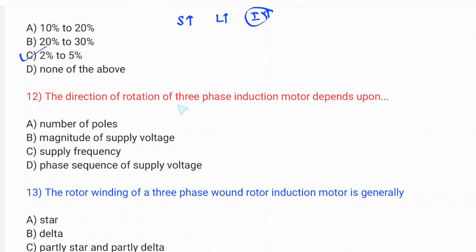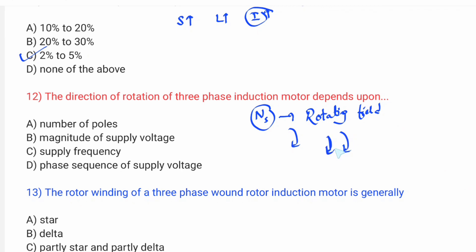Next question: the direction of rotation of a three-phase induction motor depends on what? Direction of rotation depends on the rotating stator field direction. The rotor always follows in the same direction as the stator field. Supply voltage magnitude and supply frequency do not change the direction — but phase sequence does.